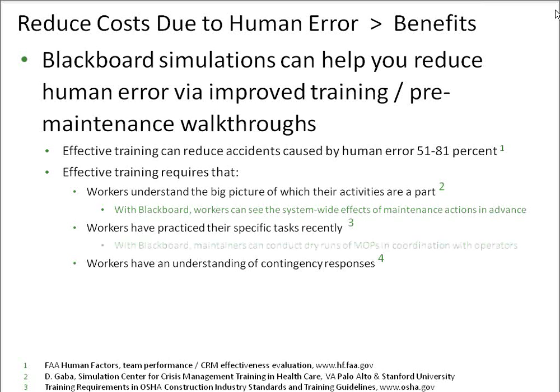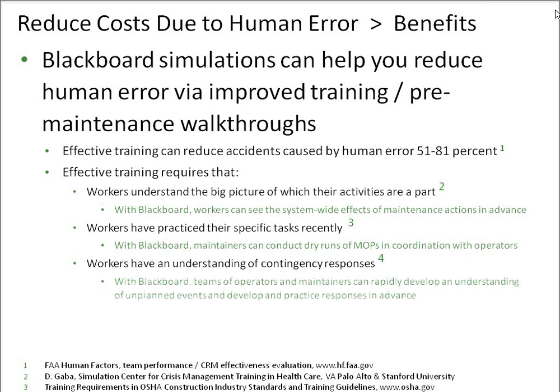There was a commissioning error that wasn't uncovered until capacity reached a certain point, and when it did, it triggered that condition, and unfortunately the staff within the data center did not respond appropriately, and an outage was created. So having the ability to model your one-line, cooling environment, etc., in a simulation environment helps eliminate those kinds of errors and ultimately gets operations staff more on their toes.